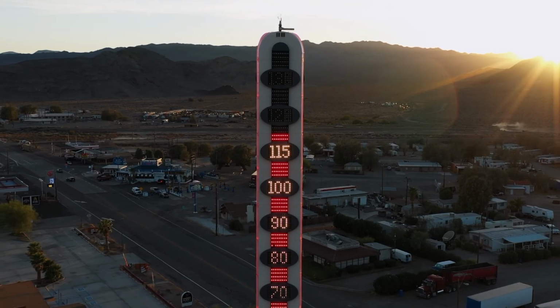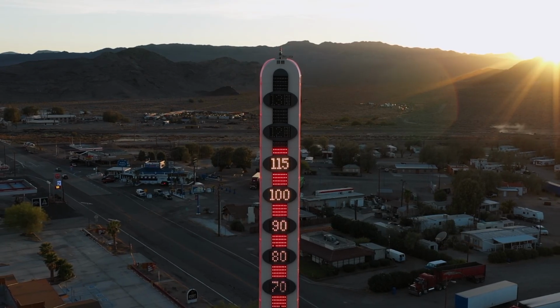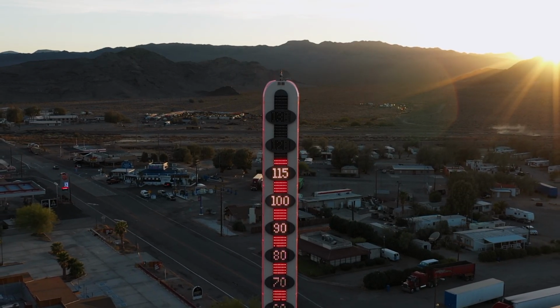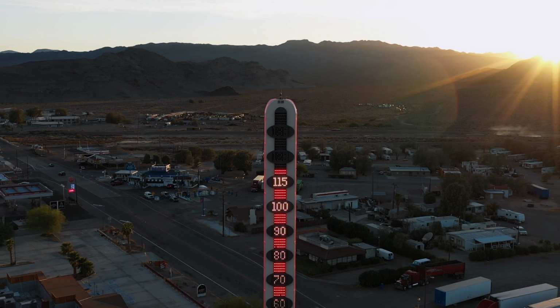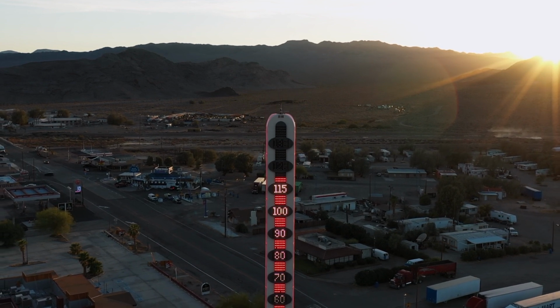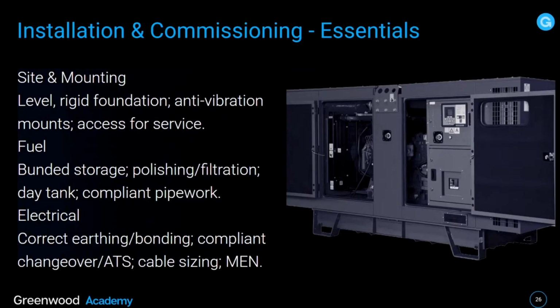So you can imagine the situation, say, in some remote areas of Australia or around the world where you're getting some fairly hot conditions, over 40 degrees centigrade or over 110 degrees Fahrenheit. An air-cooled unit really will suffer, and its ability to deliver sustained energy to loads is severely reduced compared to a water-cooled unit. Now, we're looking at installation and commissioning, the essentials.